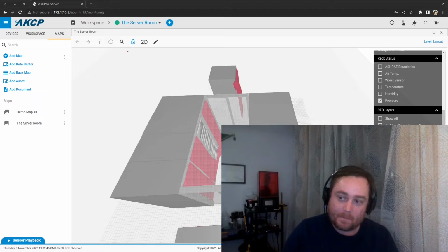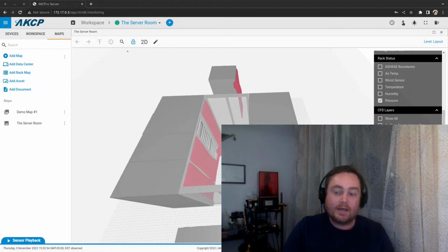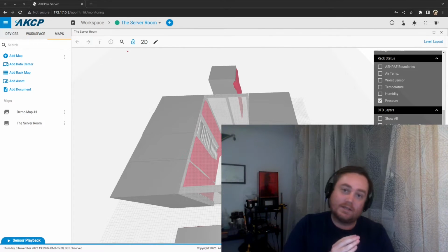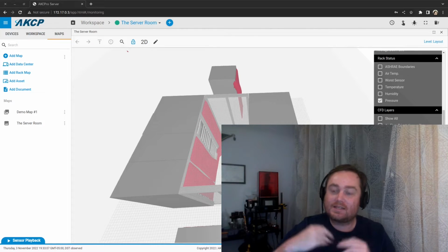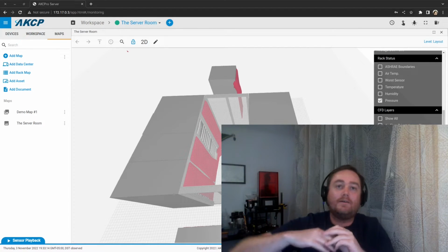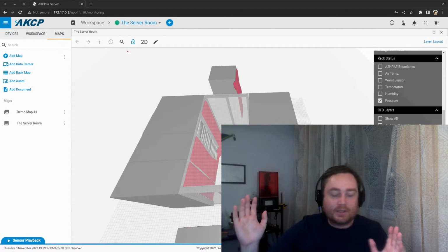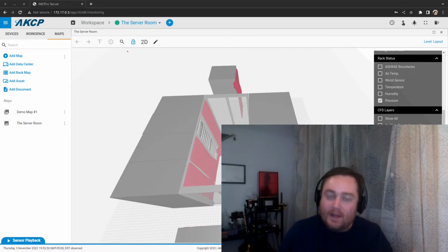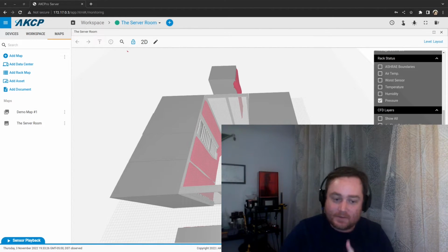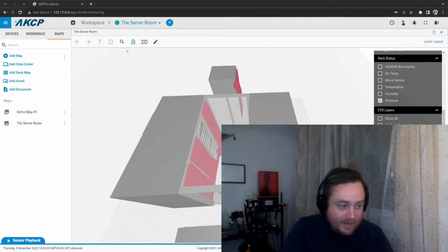Here is the clever thing. We set the boundary temperature. So the model fails, and we want it to fail because it's not reality. Something is wrong. The temperature getting in is not the temperature of the probe. So we want the user to see that something is wrong with the drawing. If we don't do that, the temperature will have 5 or 10 degrees of difference. The colors will be beautiful, everything will be beautiful, and everything goes like nothing is wrong. So we don't want that. So look at what's happening. It's really clever.